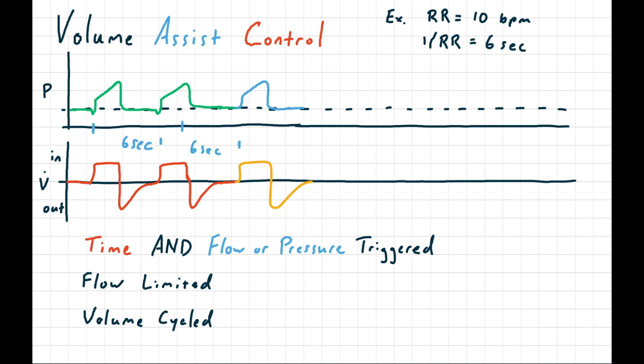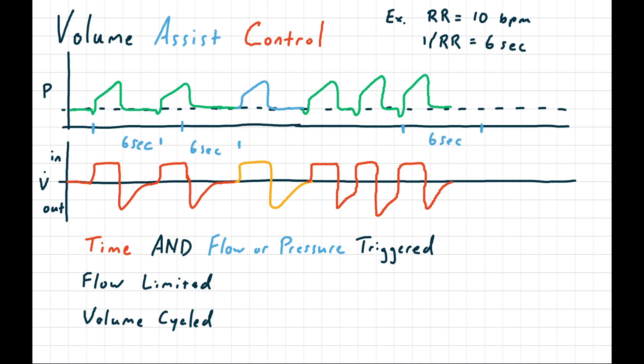One other detail: traditionally there is no restriction on how soon after one breath finishes the next can be triggered by the patient. This puts you at a theoretically high risk of auto-PEEP or breath stacking. To prevent this, ventilators have a built-in lockout window in assist mode. In addition to the six-second time trigger, the ventilator has a lockout window time within which the patient can't trigger another breath — often called a window parameter. After any breath, there's a lockout period, then a window during which the patient can trigger a breath, then a time limit after which the ventilator triggers a control breath on its own.